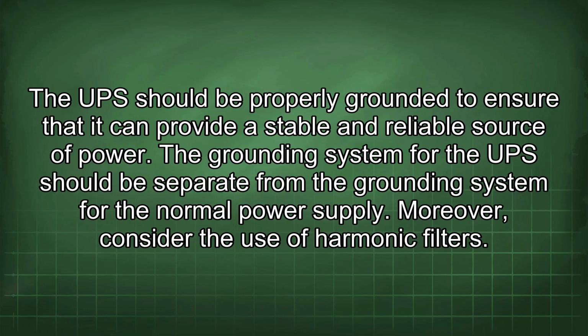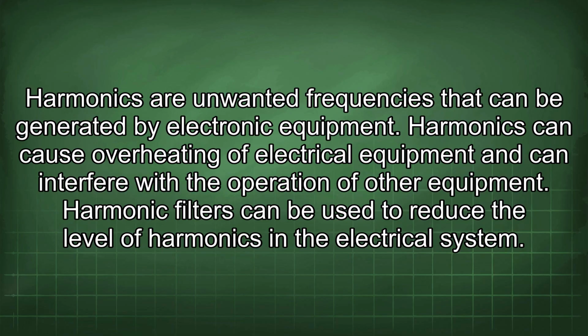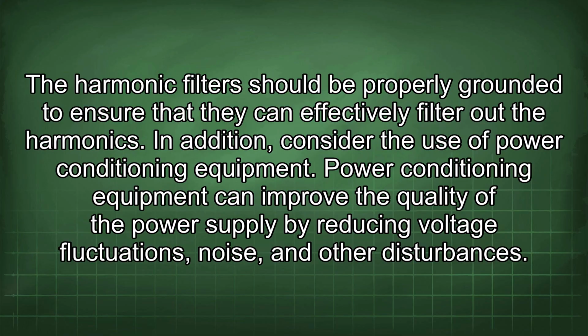Moreover, consider the use of harmonic filters. Harmonics are unwanted frequencies that can be generated by electronic equipment. Harmonics can cause overheating of electrical equipment and can interfere with the operation of other equipment. Harmonic filters can be used to reduce the level of harmonics in the electrical system. A harmonic filter should be properly grounded to ensure that it can effectively filter out the harmonics.